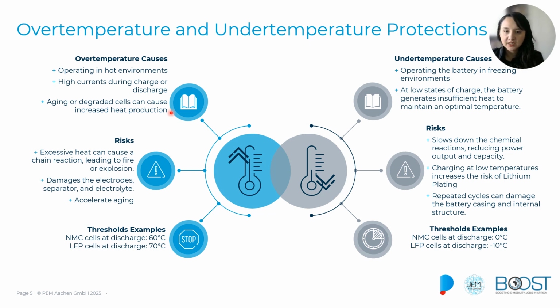So it is important to operate the battery within the specified temperature range to avoid our battery degrading faster than expected. The BMS monitors the cell and the pack's temperatures and will respond in case of these events, for instance, by activating the cooling system to dissipate the heat, and also by reducing the charge and discharge currents to minimize the heat generation. Ultimately it will disconnect the battery entirely if the temperature exceeds the critical limits. Again, the thresholds will depend on the chemistry, on the cell, and also on the mechanical and thermal design of our full battery pack. We also have problems with under temperature, and we also have under temperature protections.